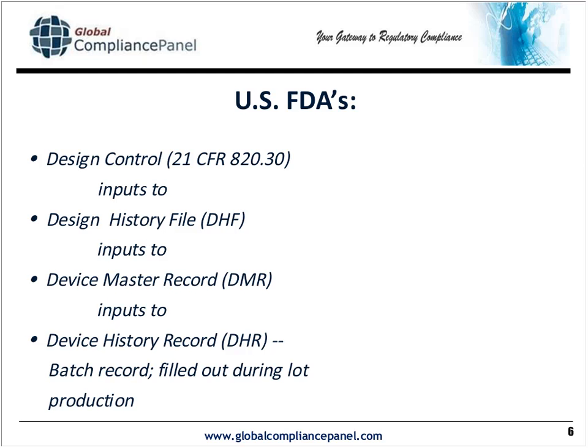The design history file includes the developmental history of the documentation that ultimately becomes part of the device master record, which would be your SOPs for assembly, SOPs for testing, drawings, schematics, production equipment that's unique to that piece of equipment, etc.